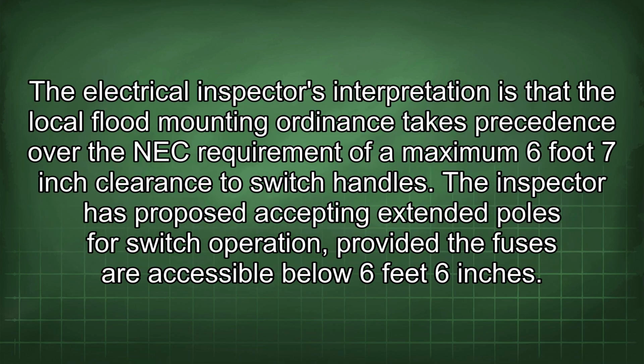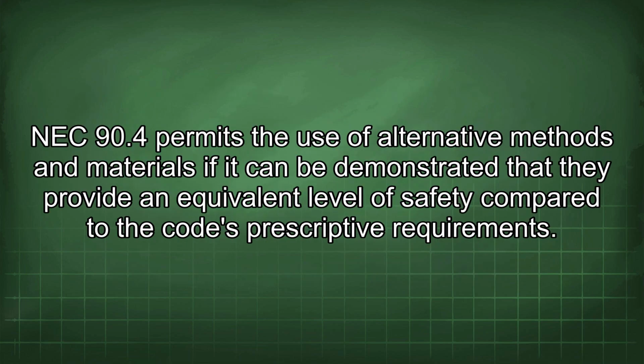The electrical inspector's interpretation is that the local flood mounting ordinance takes precedence over the NEC requirement of a maximum 6 foot 7 inch clearance to switch handles. The inspector has proposed accepting extended poles for switch operation provided the fuses are accessible below 6 feet 6 inches. NEC 90.4 permits the use of alternative methods and materials if it can be demonstrated that they provide an equivalent level of safety compared to the code's prescriptive requirements.